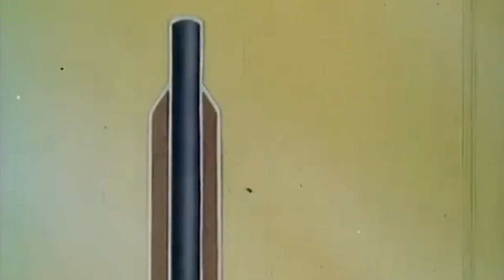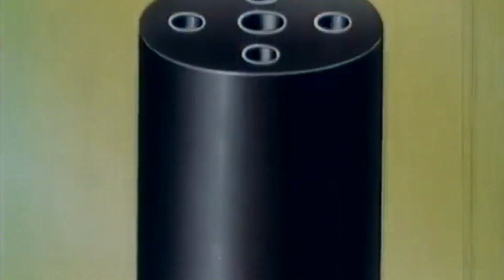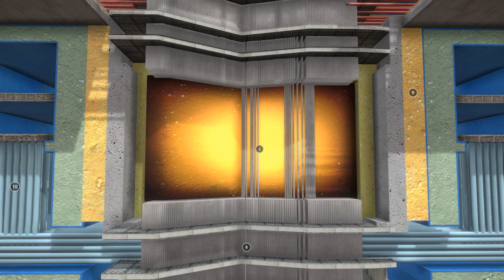The explosion was a result of a design error in the control and protection rod system, known as the end effect. It caused a rapid and short-term increase in reactivity and therefore power, while the neutron-absorbing rods should have reduced this reactivity. The graphite displacers, located in the central part of the active zone, were fully lifted by the rods.